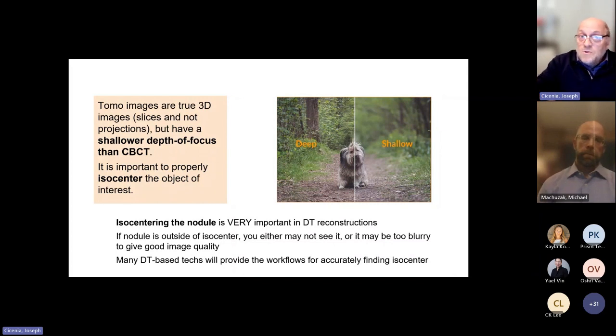With DT or tomo, because you have a limited angle sweep, the images coming through all intersect as you go around - that's called isocenter. The image that occurs at isocenter is very detailed, and the further back you go, it becomes more blurry. We call that a shallower depth of focus.